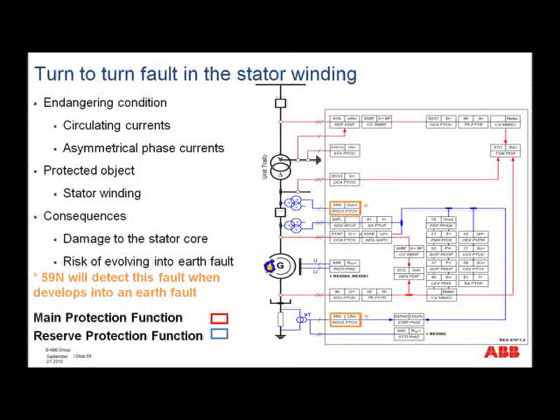But what is perhaps not shown on the slide is, and remember I was speaking about this negative sequence function, in particular the negative sequence sensitive function that now forms part of the 87G function. This function offers better possibility, more sensitivity, to detect such turn-to-turn faults than what you can get from the traditional 87G function or phase function.